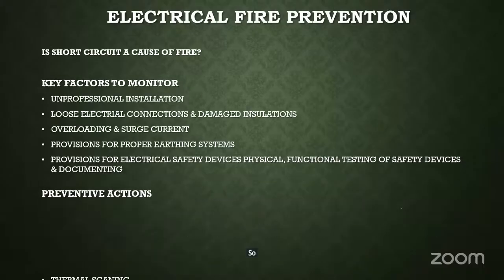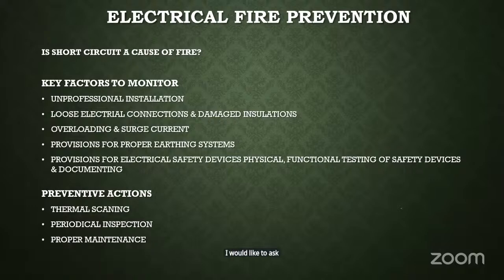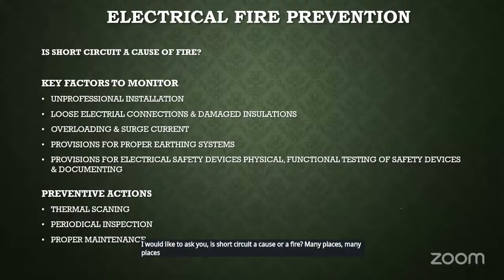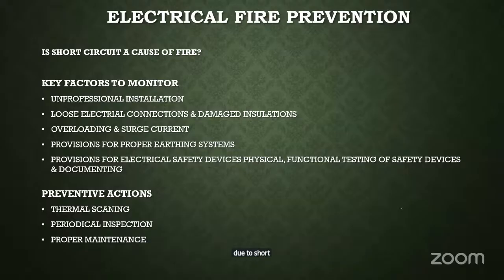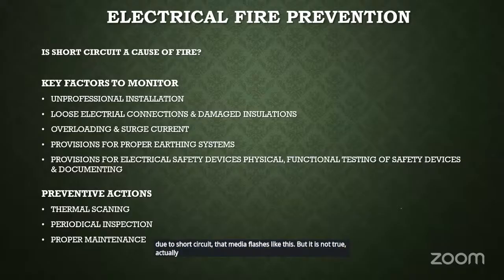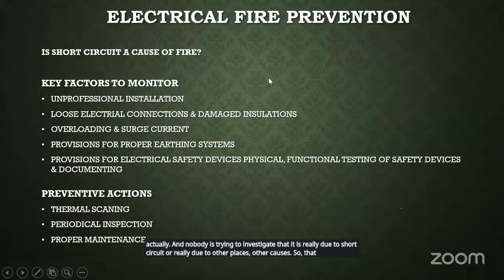So I would like to ask you, is a short circuit a cause of fire? In many places, even in the media, they claim that most fires now, to the range of 50 to 75%, are due to short circuit. The media flashes like this. But it is not true, actually. And nobody is trying to investigate whether it is really due to short circuit or due to other causes. We just ascribe that short circuit is the culprit, simply say so and pass on the incidents.